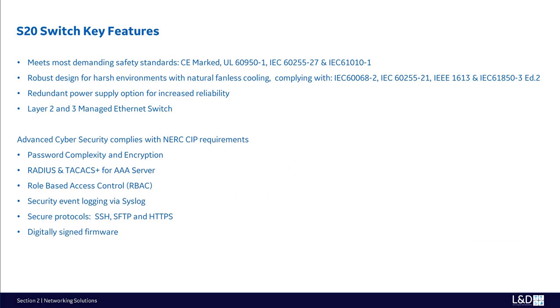The S20 switch delivers full cybersecurity features that help operators comply with NERC CIP guidelines and regulations by supporting core features such as password complexity and encryption. The factory default password is different for each manufactured device, and after the first login, users must change the password with at least 8 characters, including lowercase and uppercase alphabets, numeric, and special non-alphabet characters. Passwords are encrypted using SHA 256 by default.